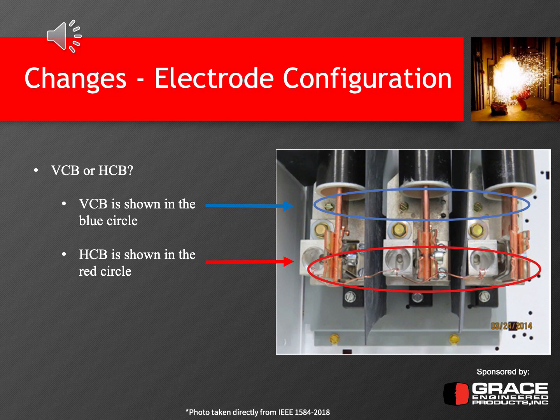So here's an example of an installation that could have multiple electrode configurations, where you would need to calculate the arcing current and the incident energy based on these different electrode configurations. So is this a VCB or is this an HCB? If you look at the blue circled area where the blue arrow is pointing, VCB is shown because it's a vertical conductor that's not open air and it's not going into a barrier. So it's a VCB installation, while it also has an HCB installation because of these stabs that the device connects into, and that's a pretty large difference between the two. So I just want to say that the electrode configuration could change based on how it's actually installed. That's very important information to gather when performing these arc flash studies.